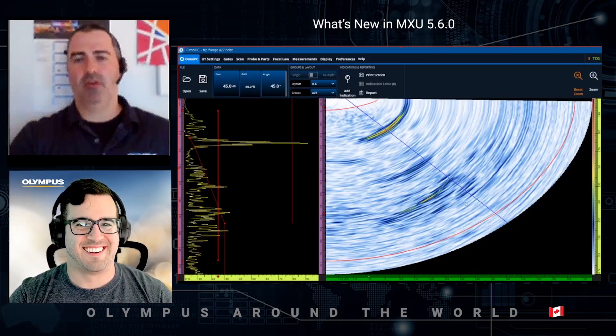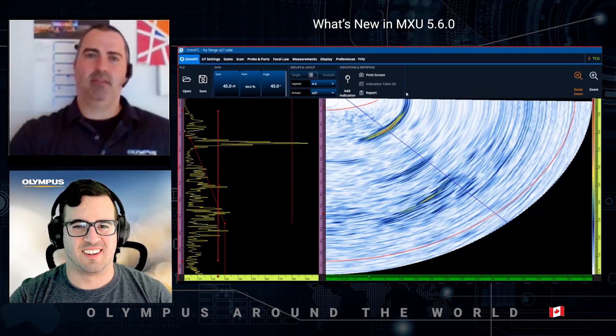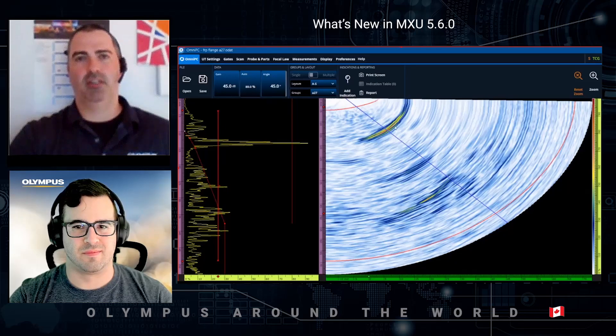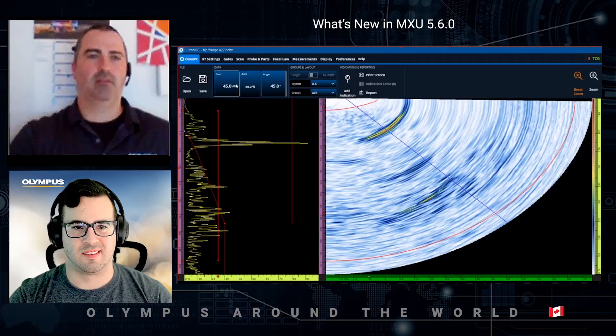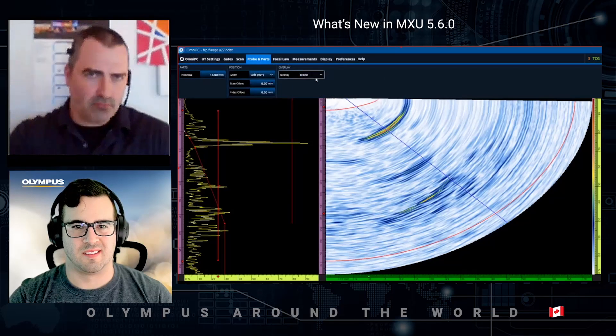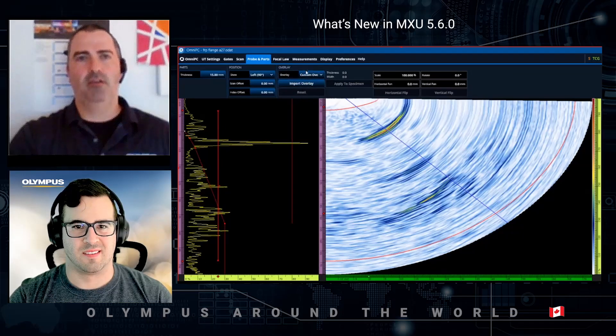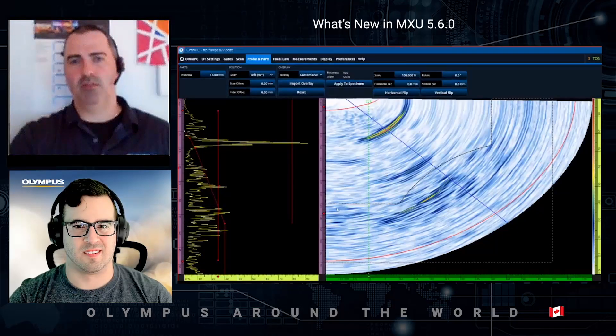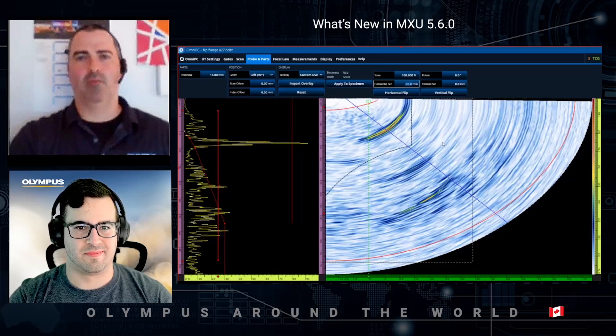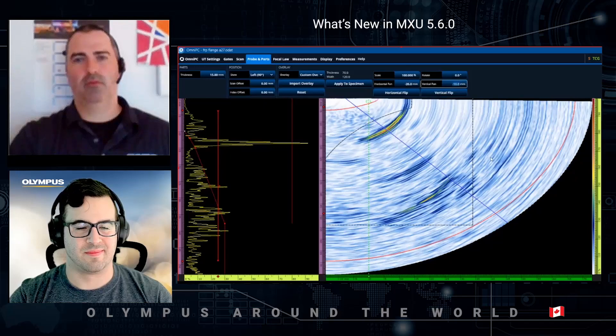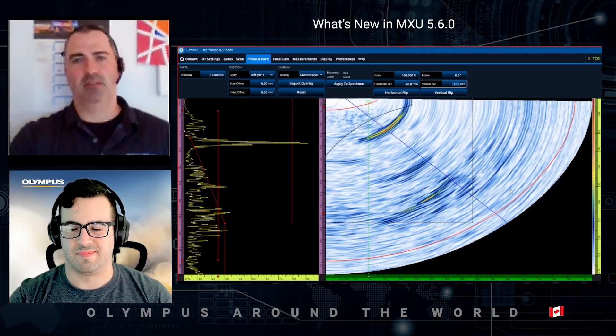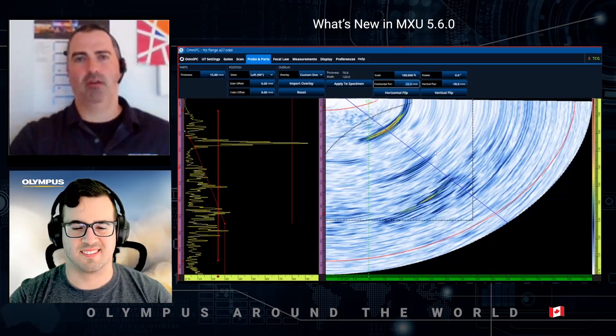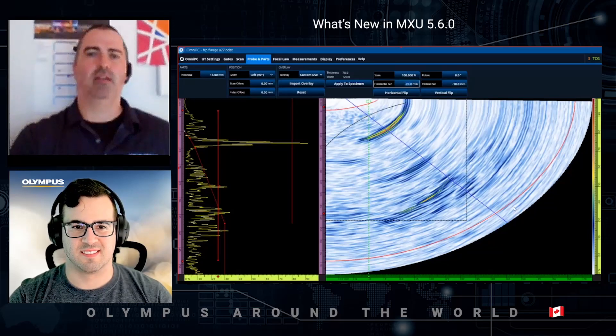Here I have a manual inspection of an FRP flange. The flange is cracked on top and there is quite a bit of corrosion in the inside corner. To make this more obvious, we can import 2D CAD drawings in DXF format. Just select the correct overlay — here it's FRP flange — and the 2D drawing gets imported. From there I can adjust the X and Y axes to reflect where the probe and signal were positioned, making it easier to see where the crack is located and how deep the corrosion goes.